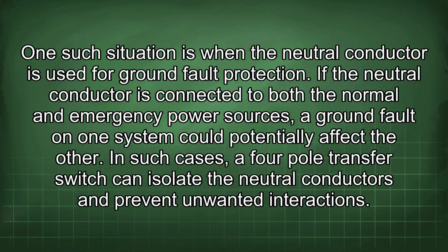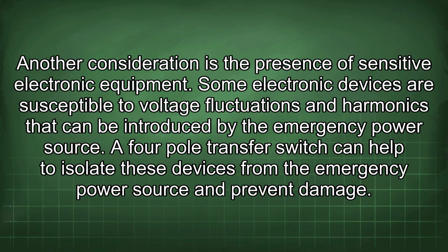One such situation is when the neutral conductor is used for ground fault protection. If the neutral conductor is connected to both the normal and emergency power sources, a ground fault on one system could potentially affect the other. In such cases, a 4-pole transfer switch can isolate the neutral conductors and prevent unwanted interactions. Another consideration is the presence of sensitive electronic equipment. Some electronic devices are susceptible to voltage fluctuations and harmonics that can be introduced by the emergency power source. A 4-pole transfer switch can help to isolate these devices from the emergency power source and prevent damage.